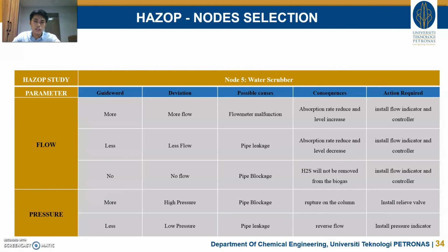Next node is water scrubber. For more flow, cause flow meter malfunction. Consequence, absorption rate reduced, level increase. Action required, install flow indicator and controller. Less flow, the possible cause is pipe leakage. Consequence, absorption rate reduced and level decrease. And action required is to install flow indicator and controller.